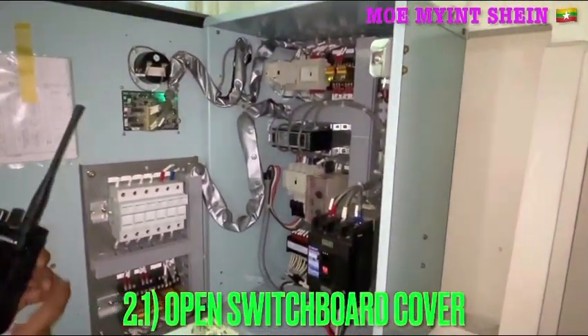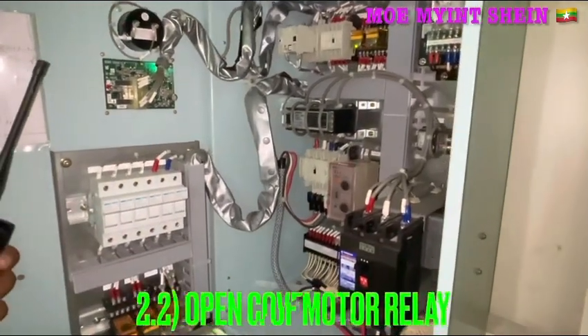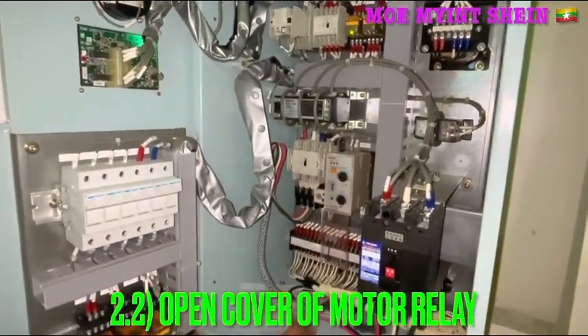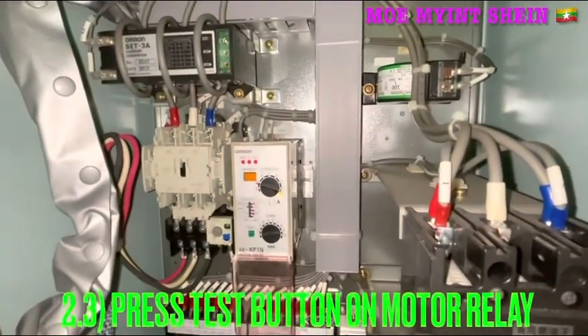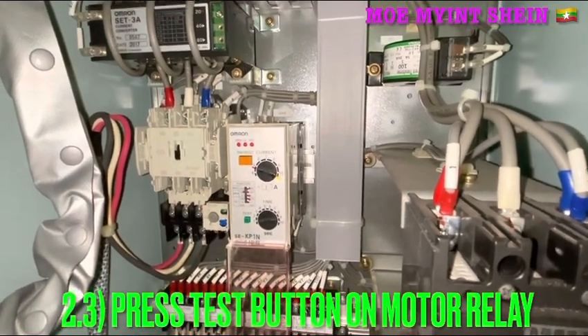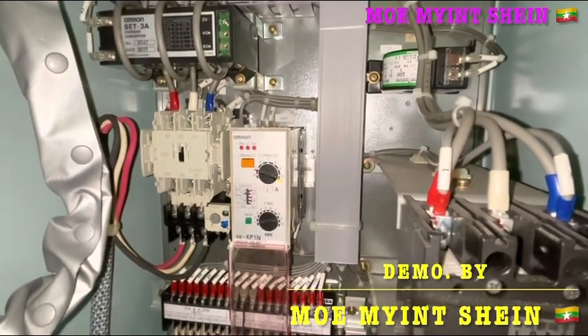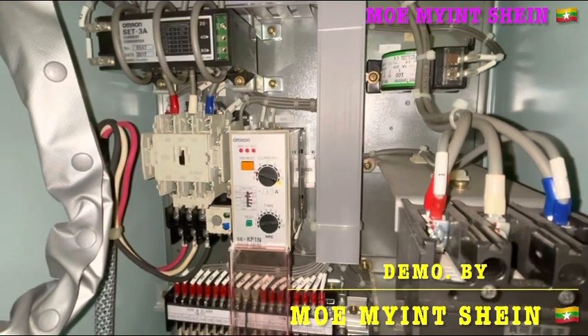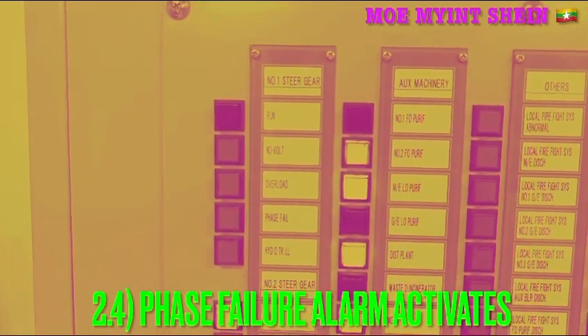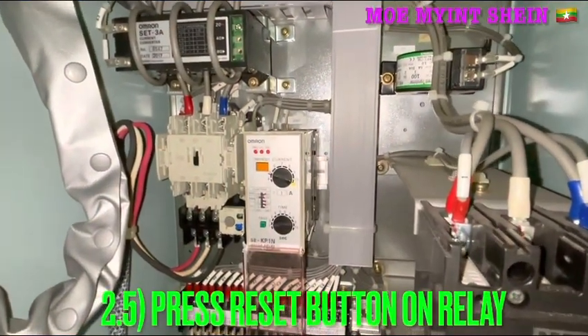Now let's carry out the phase failure alarm testing. Open the panel cover and check the communications between the engine control room and steering gear room. Open the cover of the relay, then press the test button on the relay. Confirm phase failure alarm activation in the engine control room, then push the reset button to reset the alarm.